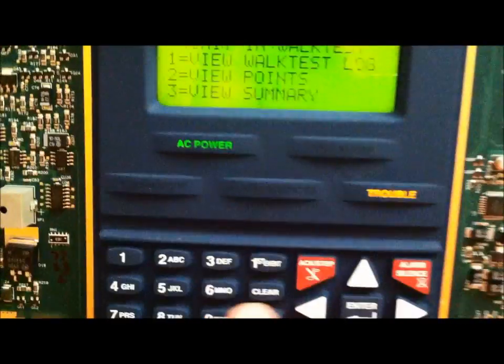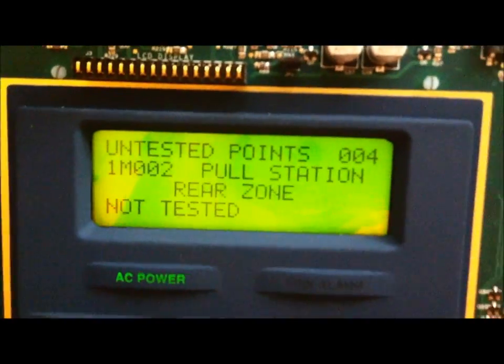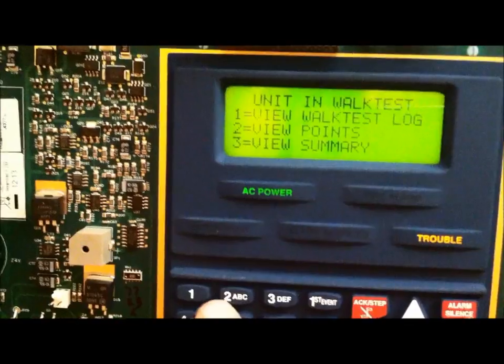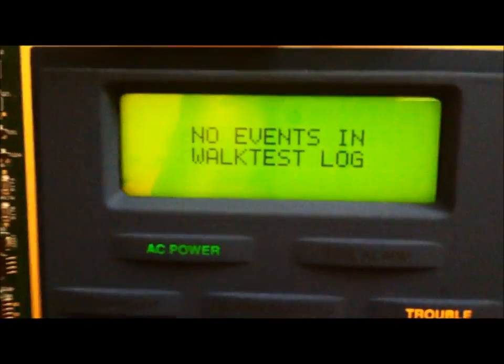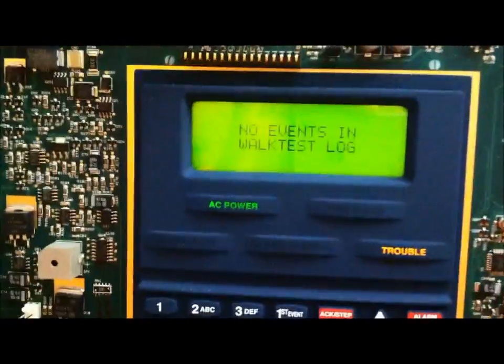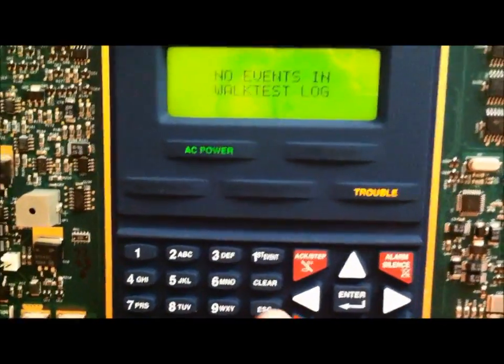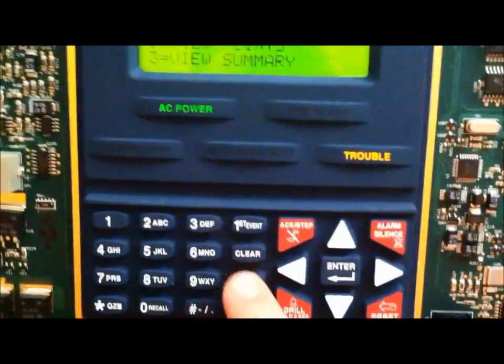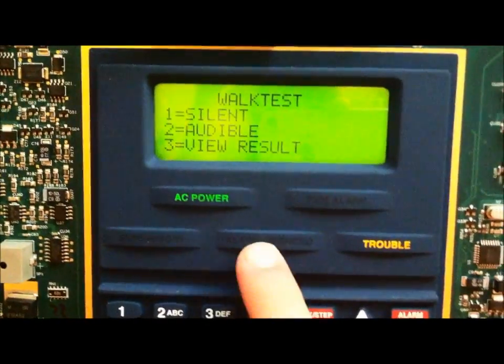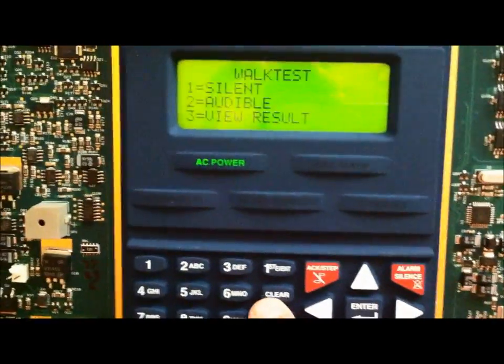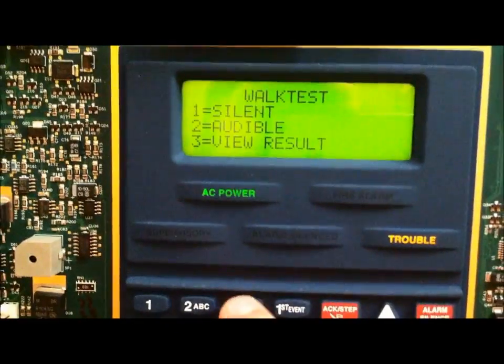Let me go ahead and go back. If I were to go to view points, this shows all of the untested devices. And if I were to go to view walk test log, nothing is in history because I have not tested any devices, but it would show you all of the tested devices. Once you leave walk test mode, all of this is erased from the memory. But, you can still go to view results to view all of the tested devices.